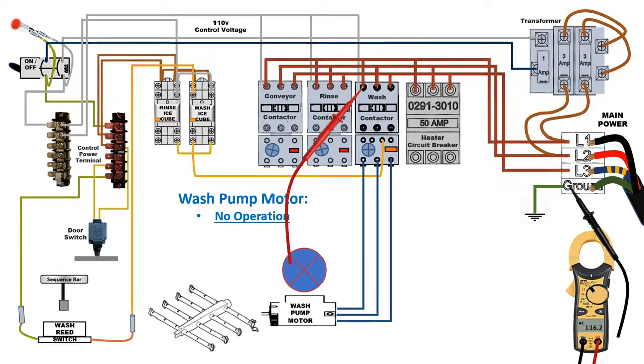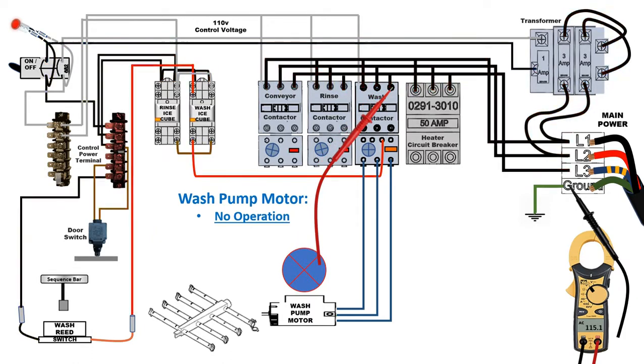Our first step is we're going to use our multimeter set to AC voltage, one meter lead to ground, and the other meter lead to the L1 position. We're going to test L1, L2, and L3 to verify if we have main power coming into the top of the contactor. Here we're showing correct voltage coming in.